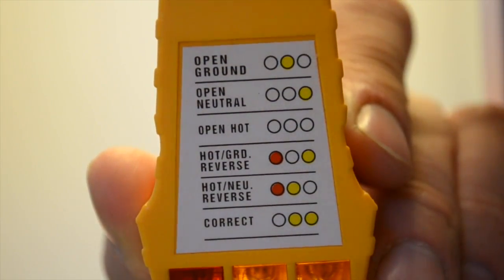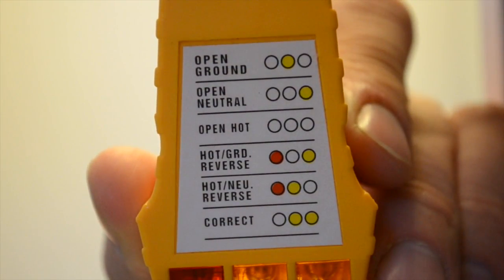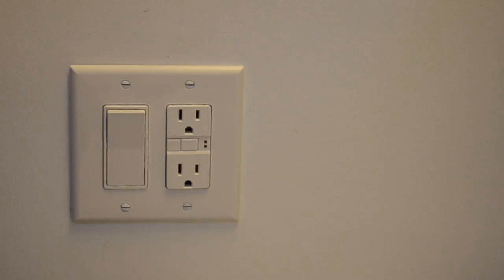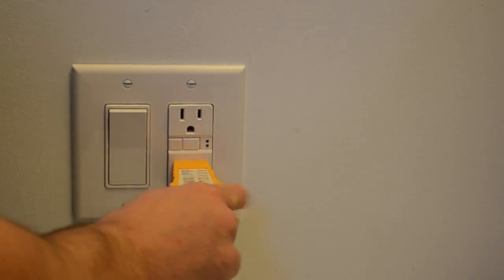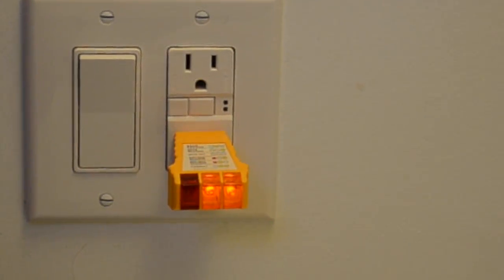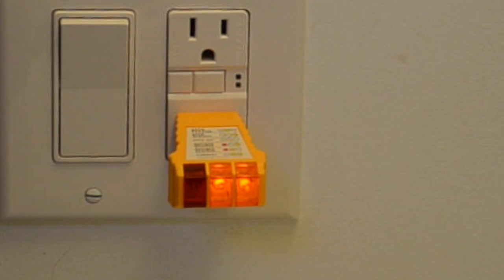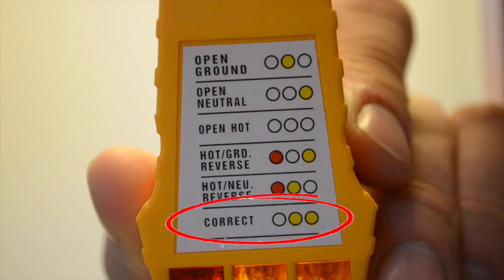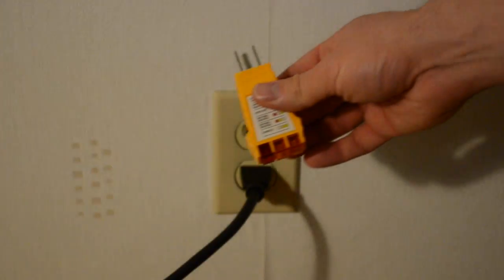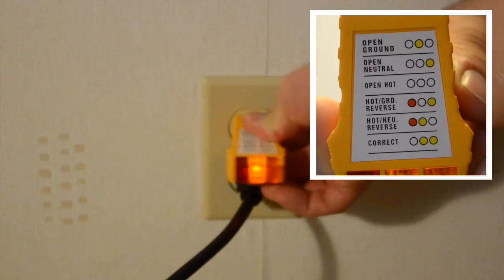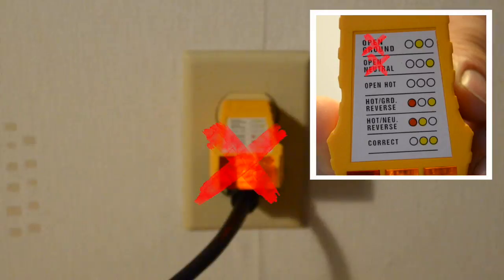Observe the label on the Smart Tester and notice the legend. Plug the Smart Tester into the outlet and observe the light indicators. 2 amber lights indicate a correctly wired ground connection that is safe to use and is the only indicated condition to proceed with. If any other indication is shown, do not use the ground source as it may be a safety concern and will not provide a connection to the earth.